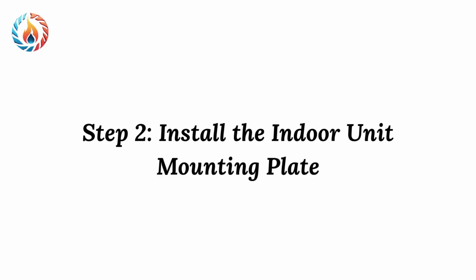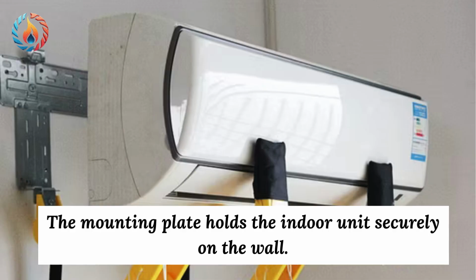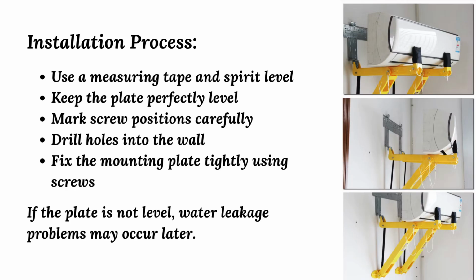Step 2. Install the indoor unit mounting plate. The mounting plate holds the indoor unit securely on the wall. Installation process. Use a measuring tape and spirit level. Keep the plate perfectly level. Mark screw positions carefully. Drill holes into the wall. Fix the mounting plate tightly using screws. If the plate is not level, water leakage problems may occur later.